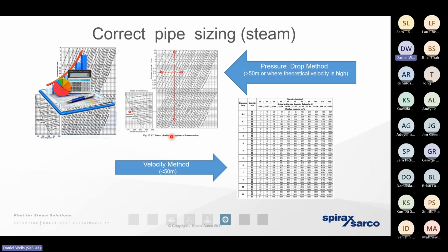I don't want this slide to scare you. It really just reminds us that there is a methodology we need to employ when we're sizing the steam pipeworks. When we're sizing in accordance with the pressure drop method at the top of the screen, it means we need to take into account the mass of steam that we're moving. We need to take into account the boiler pressure and then the pressure at the heat exchanger, the reduced pressure. But we also need to take into account the resistance in the pipework in the middle. That's what's going to result in the movement of the steam around the infrastructure. The velocity method that you can see in the bottom right-hand corner, that's really the speed that the steam's moving at.